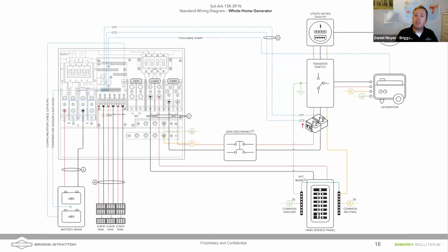Another reason you wouldn't land a generator on the gen port is if you want a much larger generator than what can be handled by the gen port. But if you have an existing generator on site and an existing transfer switch, this may be the best way to do it. You just leave the transfer switch in there, already being fed down, and you can have that easy kind of install.